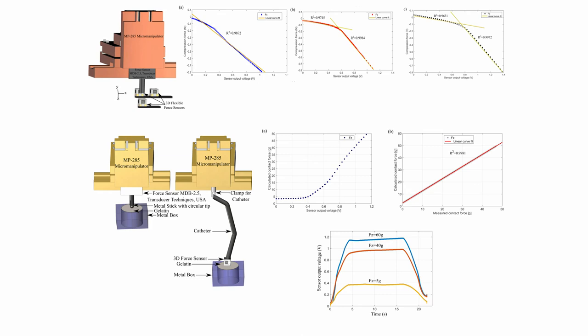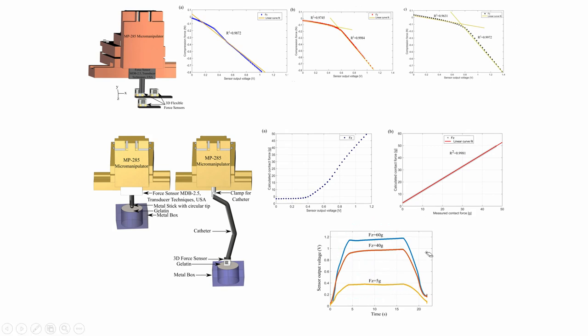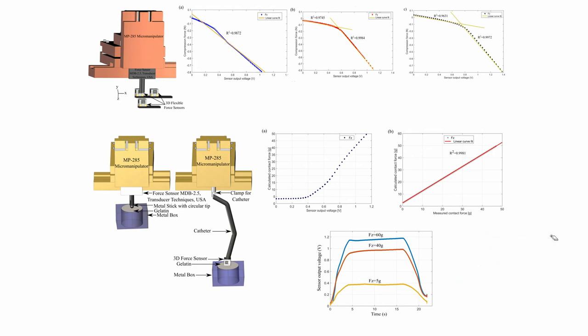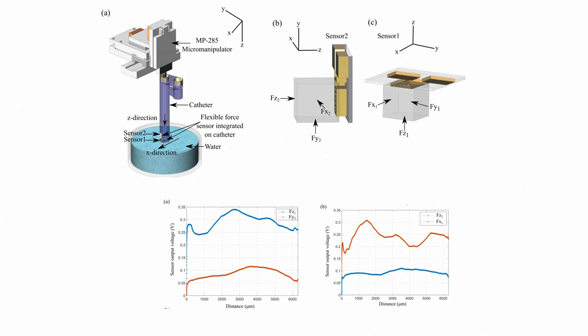For example, applying 5 grams of force and removing it shows the response time; the same is done for 40 grams and 60 grams, confirming the sensor measures from 5 grams to 60 grams. The optimum ablation force on the heart is around 35 to 40 grams. So when the catheter is ablating heart tissue, the ablation force should not exceed 35 to 40 grams. When the catheter is inserted inside the heart through blood vessels, the sensor's behavior in a liquid medium must also be characterized.